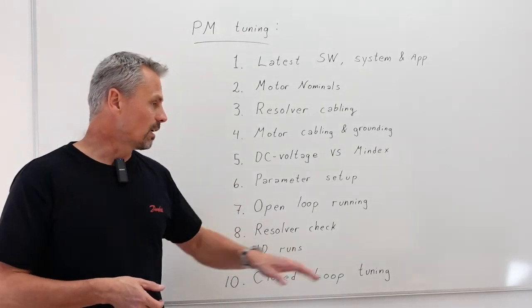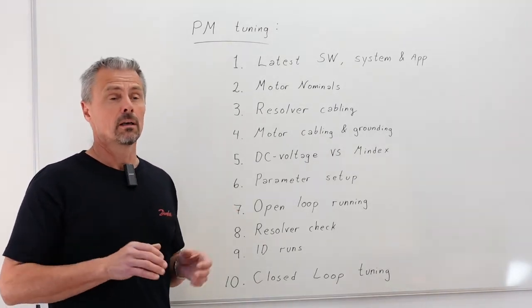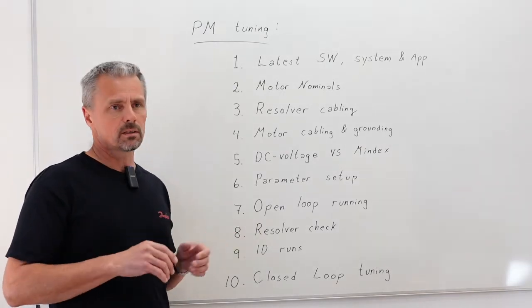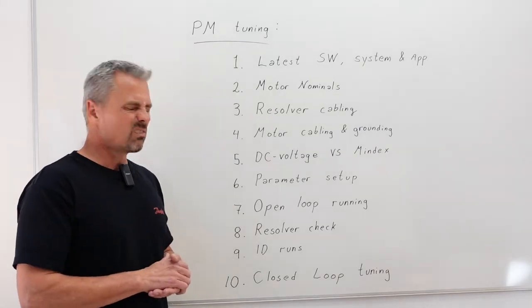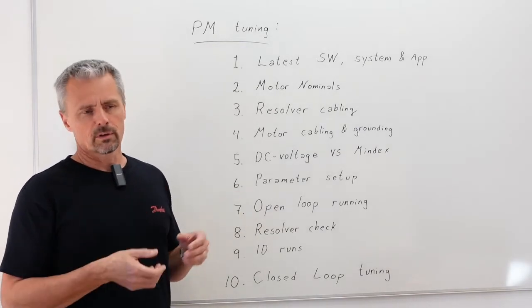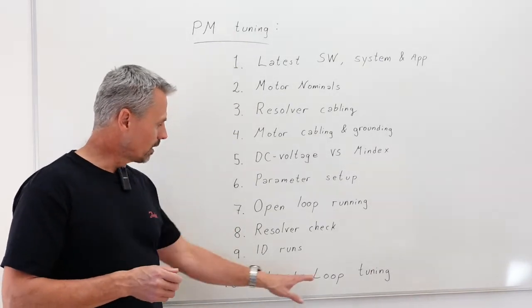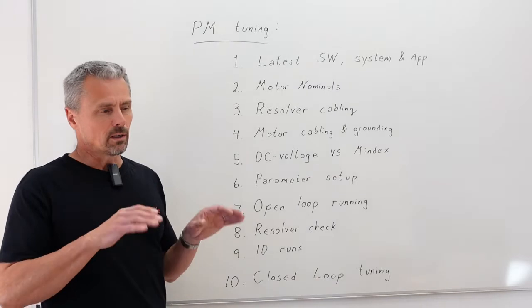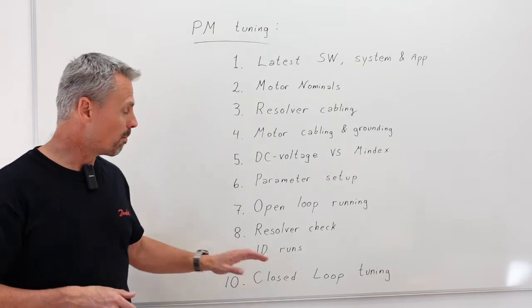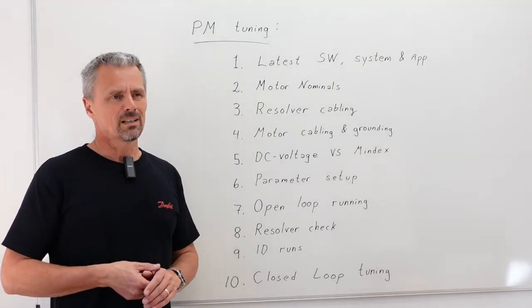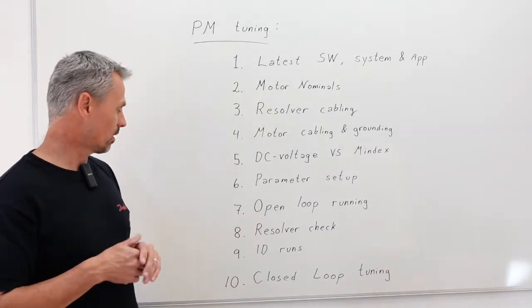Closed loop tuning - that is the final hand tuning where you adjust a little bit the amplification factors, integral times on the closed loop motor control. Take a look at filtering of the encoder signal in case you have some noise on the signal. So here you can do manual fine-tuning. Of course a lot is done with ID runs but the manual tuning in some cases will top that tuning to a smoother level.